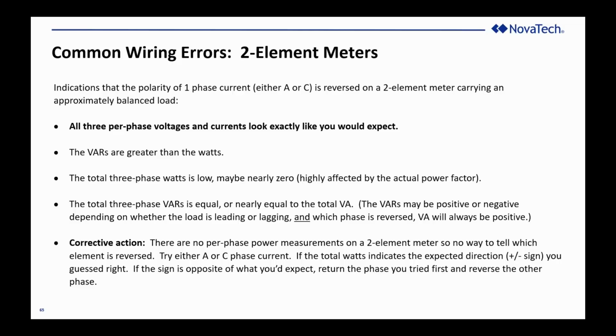So the corrective action in this case is to try either the A or the C phase current. Remember, you've got to use a sliding block or a make-before-break test switch before changing any currents, but you can reverse the polarity on either the A phase or the C phase. If the total watts indicates the opposite of what you expected, you chose the wrong phase. If it goes back to normal, that's the fix, all in one step.